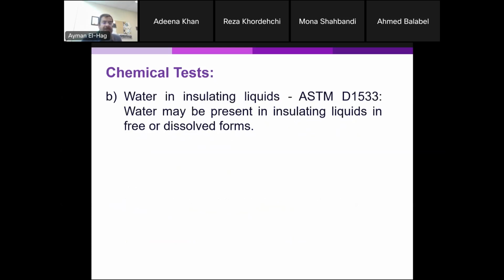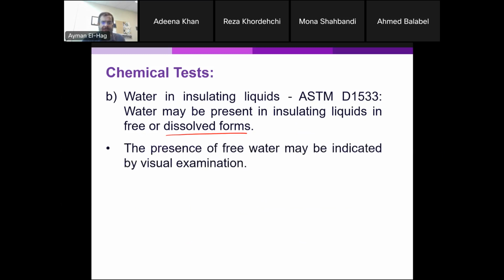Water is also measured as per ASTM standard D1533. Okay, and water can be free, and if it's free, you can easily see it, or dissolved. The dissolved form is the most common, and we cannot see it. So we measure the water content in parts per million. This is how we measure the water. And there is the Karl Fischer titration method. It's a very standard method that is used to measure the water content.